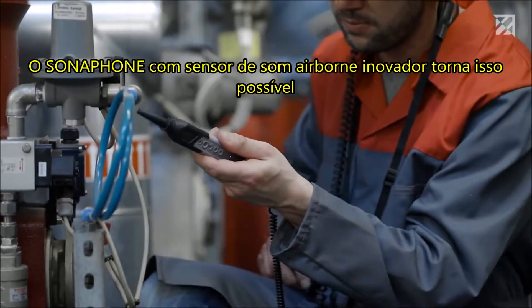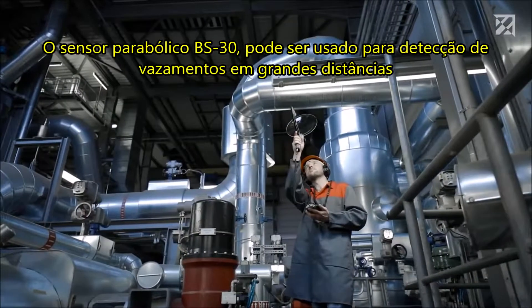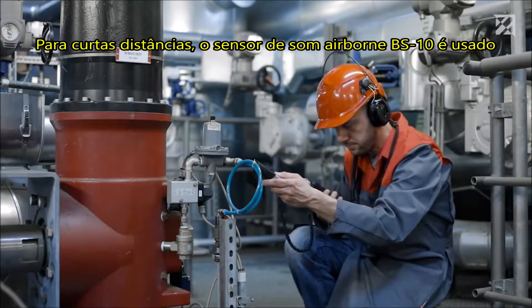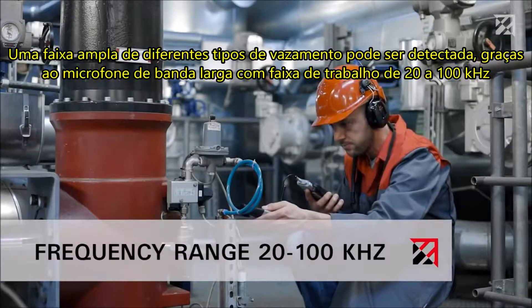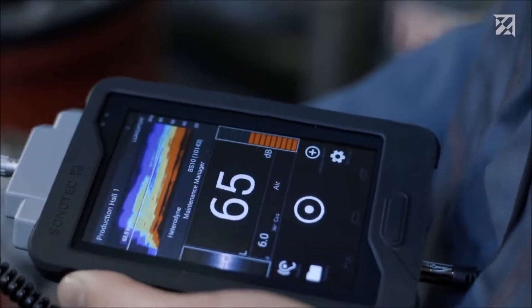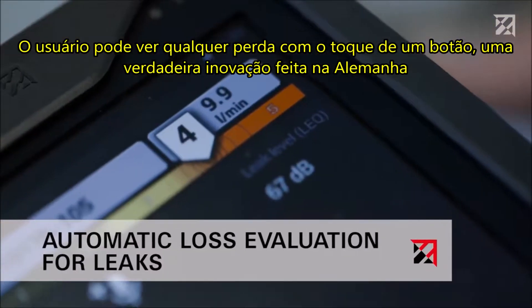The Sonaphone with its innovative airborne sound sensor makes it possible — just put on the headphones, start the app, and get searching. The parabolic sensor BS30 can be used for leak detection over large distances, while the airborne sound sensor BS10 is used for short distances. An extremely wide range of leak types can be detected thanks to the broadband microphone with a working range of 20 to 100 kilohertz. Background noise in the audible range can be suppressed, and if a leak is detected its size is also automatically assessed with the touch of a button.